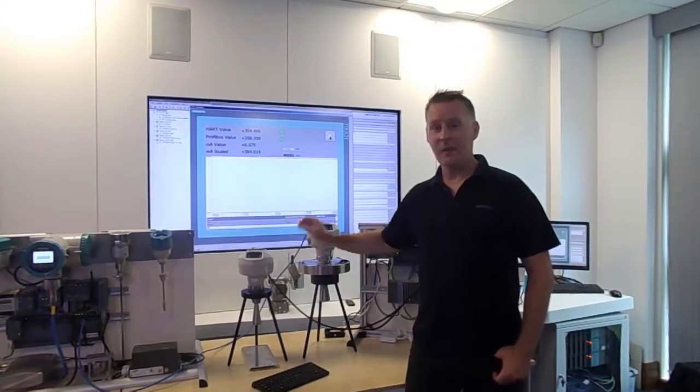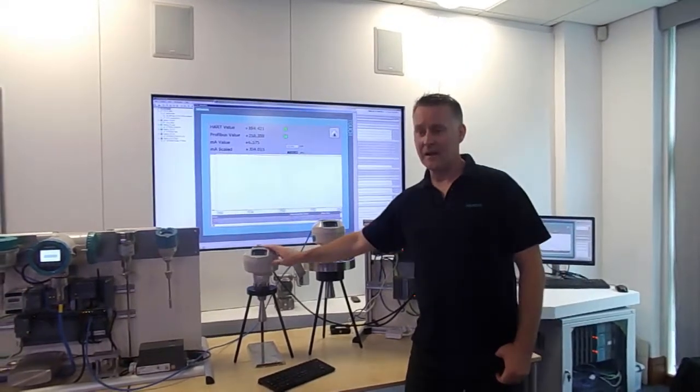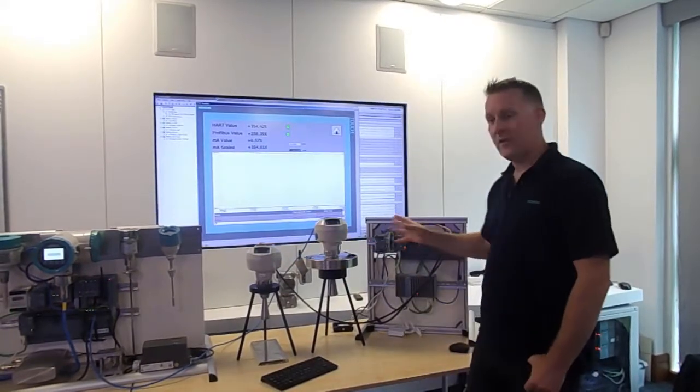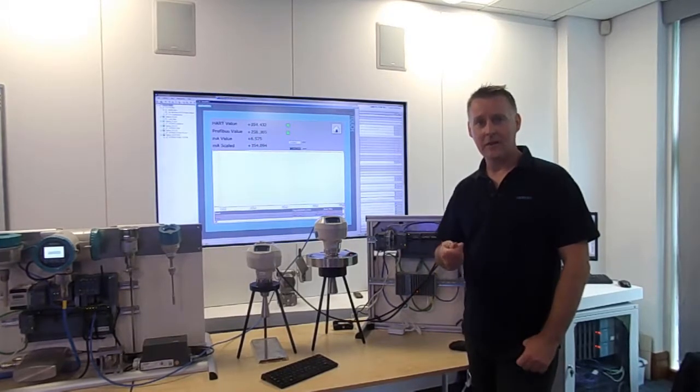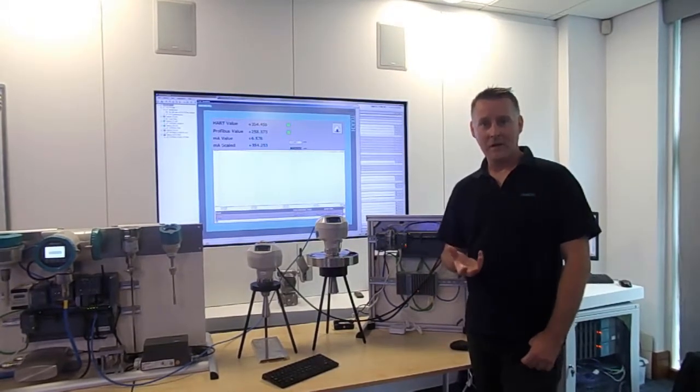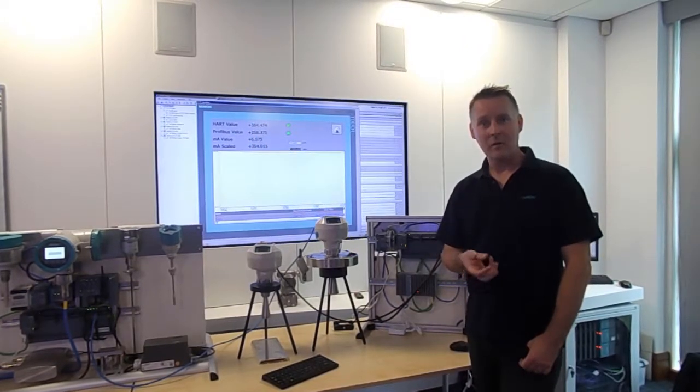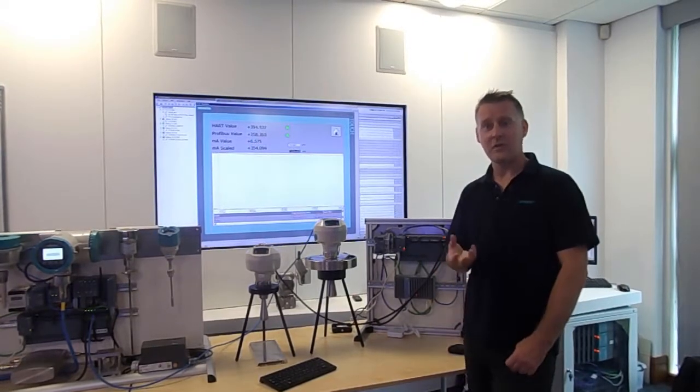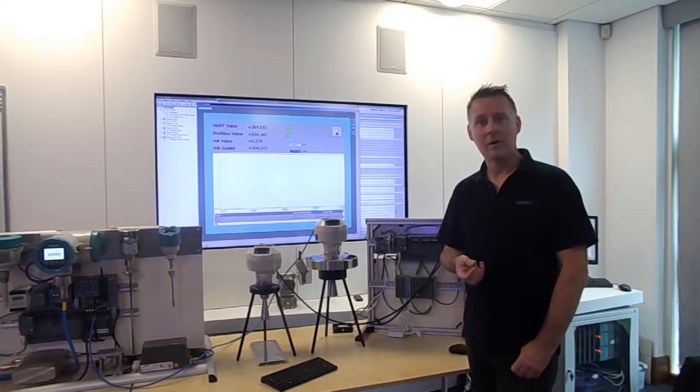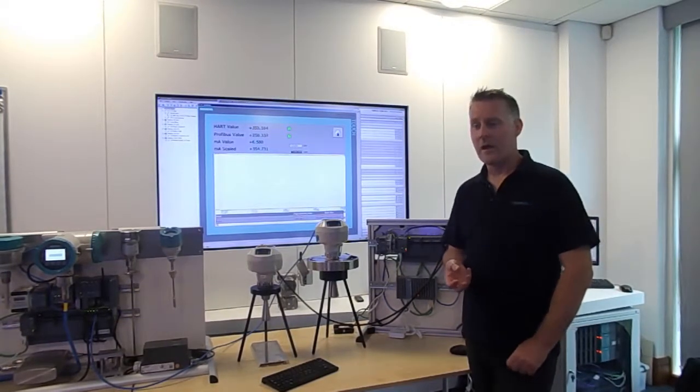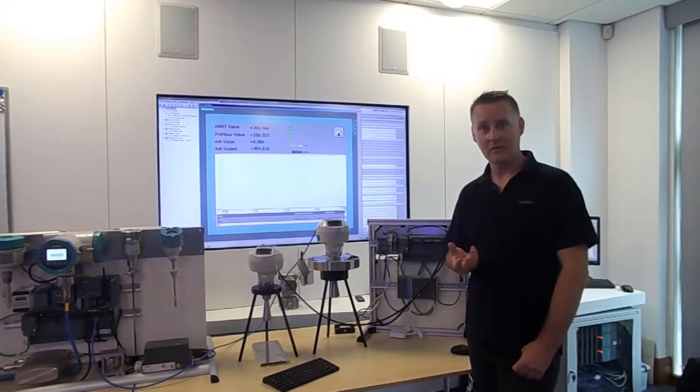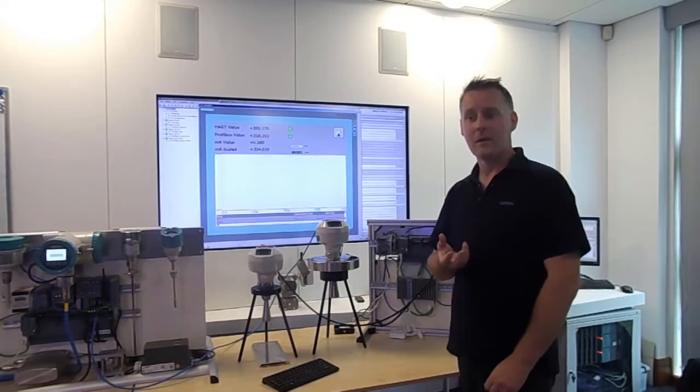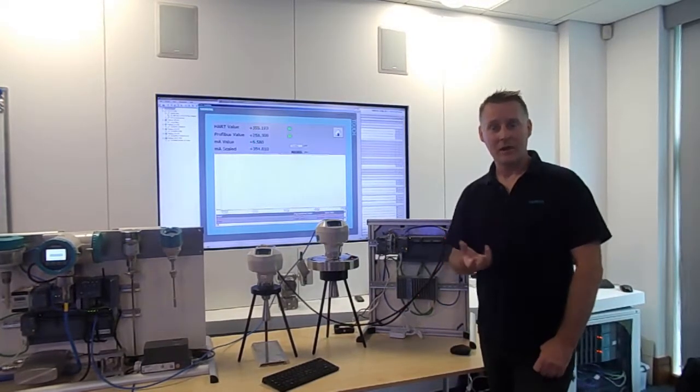So we have a milliamp radar with HART values and a Profibus PA radar connected to various I/O. The reason for doing this test is we recently had a customer who had issues with some of their radars, and when we received them back we noticed there was corrosion in the junction box. So we started to do some tests to see what would happen with condensation on different types of signals and how digital signals came out better in those tests. Over the course of this video and some videos coming up in the future we'll go into that in more detail.